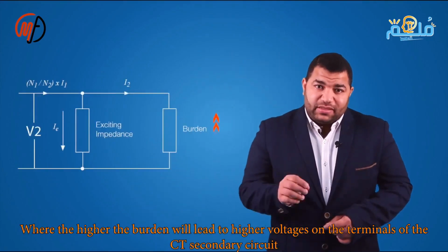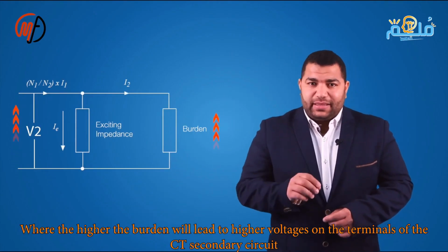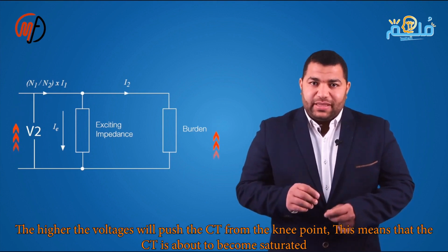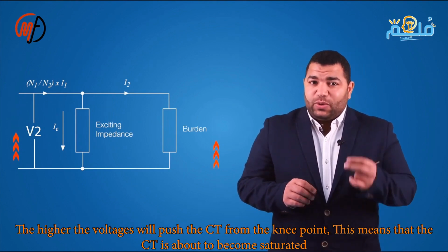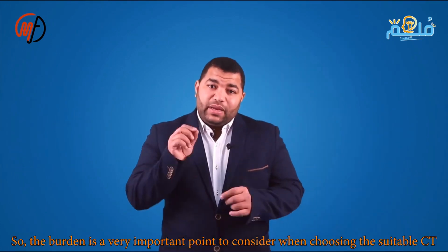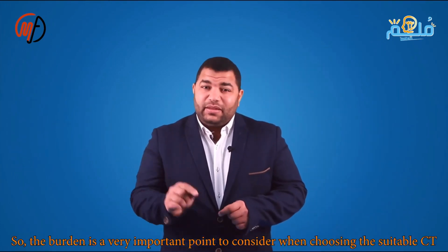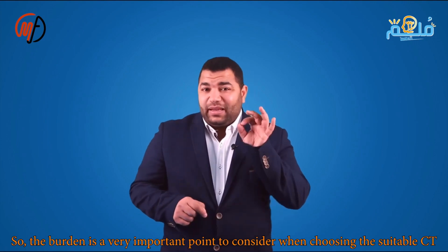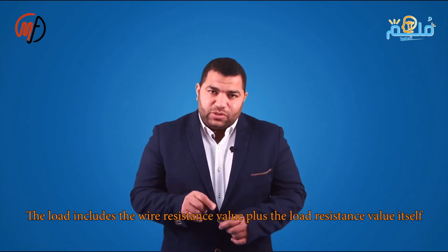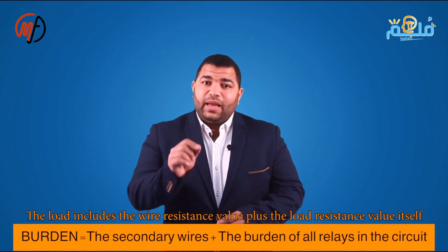As the burden increases, the voltage across its terminals rises, nearing the knee point, indicating potential CT saturation. Thus, burden is crucial when selecting a CT, including wire and relay resistance. At one station, we upgraded to digital relays, removing electromechanical ones. Post-upgrade, we advised no CT change was needed as the CT handles high and low burdens.